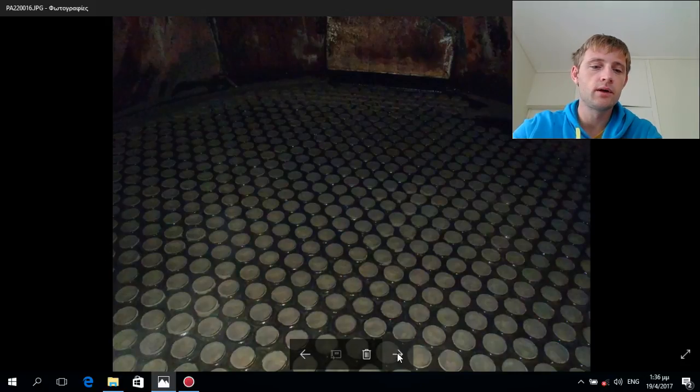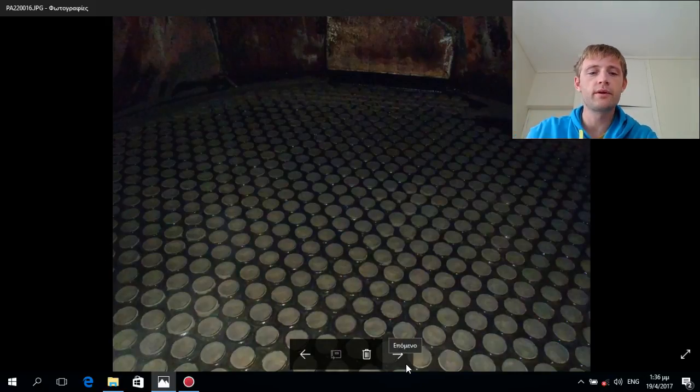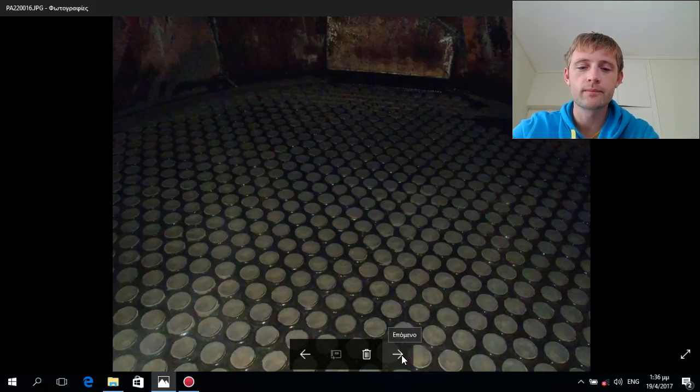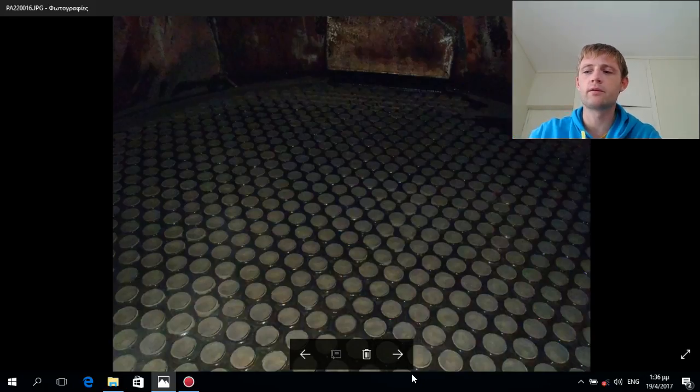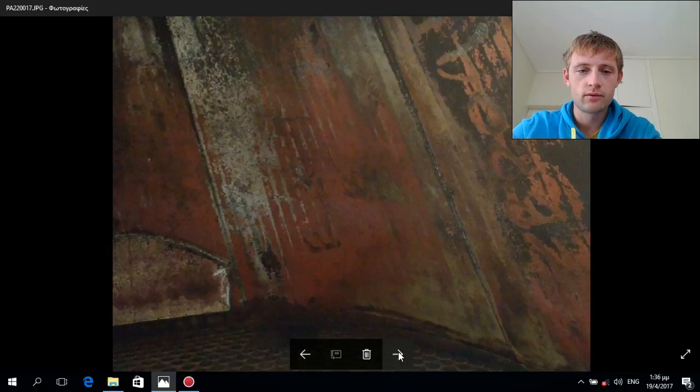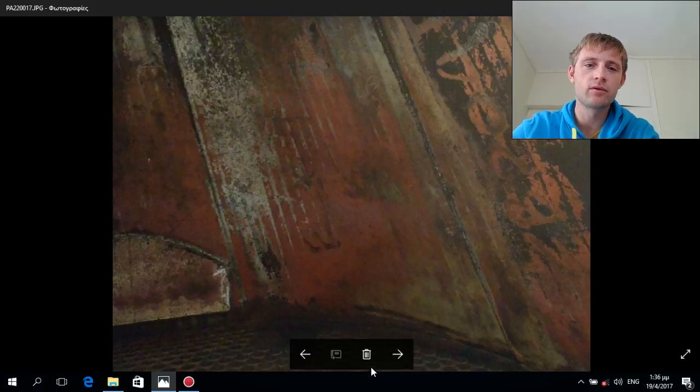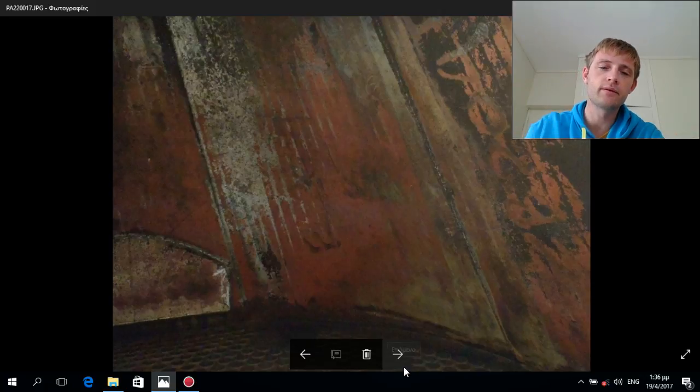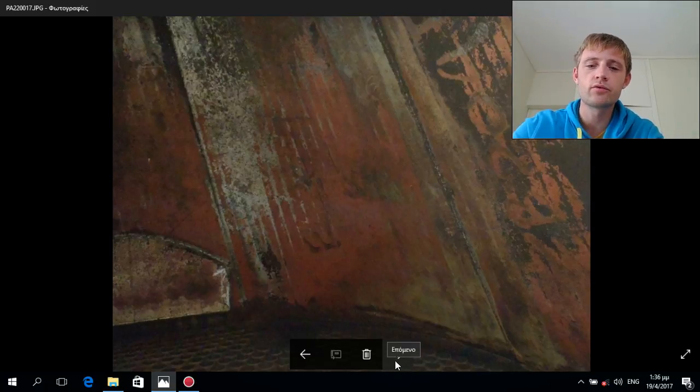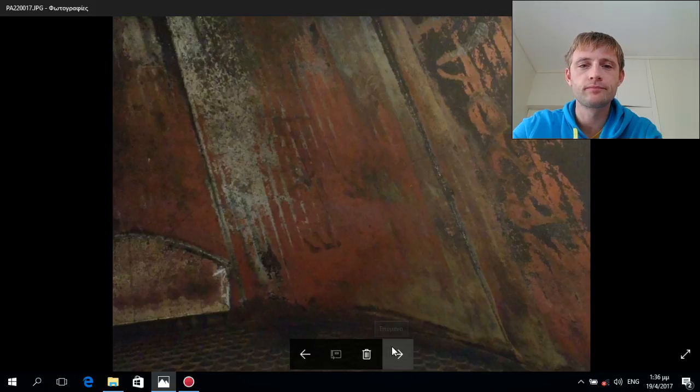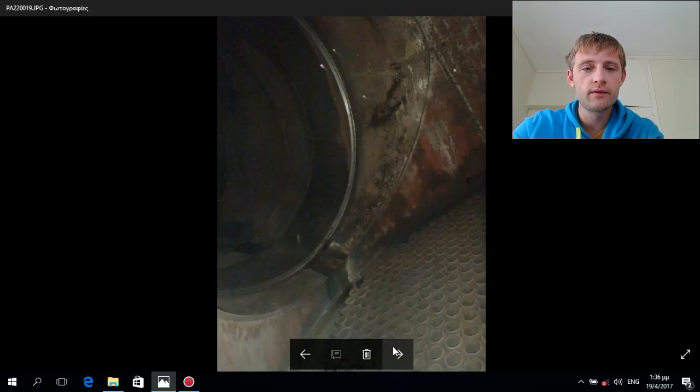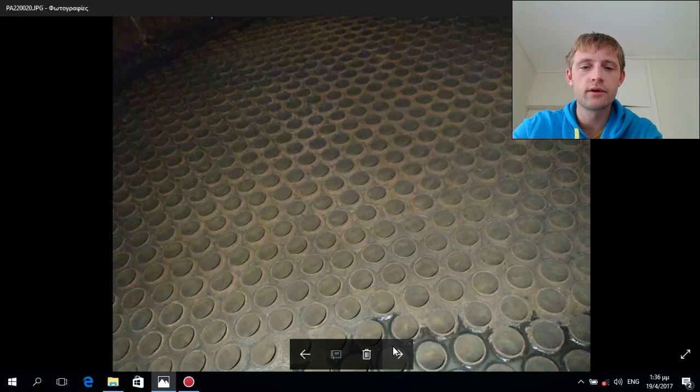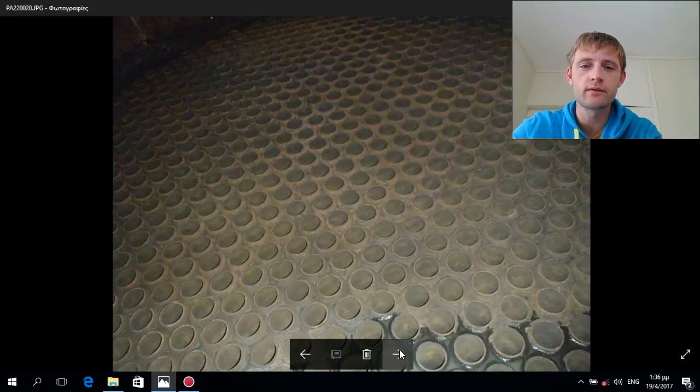And these are the tubes already washed with water one by one. It is not necessary to enter inside - you can wash from outside because also there's a high draft when you enter inside and also the temperature is very high. This is the top side of the economizer. Here you can see the tubes, the exhaust passing from inside.